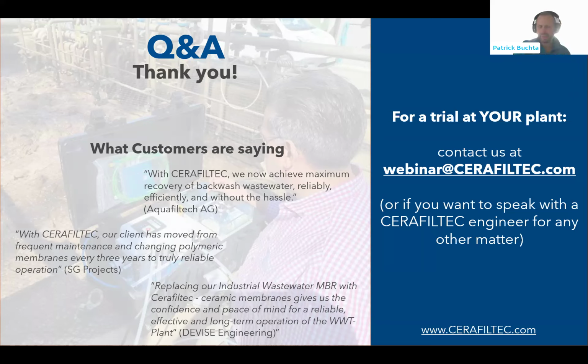That covers it very well, actually. If you talk about conventional technologies, I guess you also compare to sand filtration. Of course, there is a huge difference in filtrate quality. What you achieve with the membrane technology is a bacteria-free, particle-free water, while in sand filtration you most likely have to cover with additional pre-treatment. You need polymer dosing. You also need coagulation for the pre-treatment. It's difficult to compare one by one without knowing the project requirements. And of course, you know how it is in membrane technology. You have to pay the price for this particle-free and bacteria-free filtrate quality as well, right?